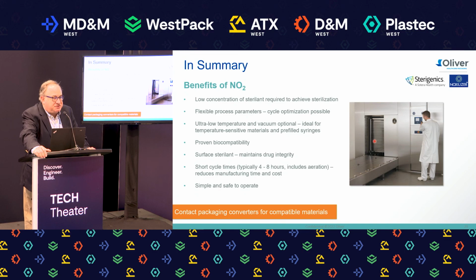As I stated earlier, just to reiterate, the way these sterilizers are designed and the process is designed, they have internal scrubber systems built into the sterilizer to absorb the NO2 sterilant that's off-gassed from the load or that's not used or picked up by the load during sterilization. So it accumulates that in a scrubber material. It also has advanced sensors so that the door will not open so that the operator gets exposed to NO2 above the TWA limit, which is 1 ppm. Once it's removed from the sterilizer, we do recommend that the load, depending on the density of the load, sit at ambient for a couple hours before you shrink wrap or package it or put it into your transportation network. That's basically it. Good question.